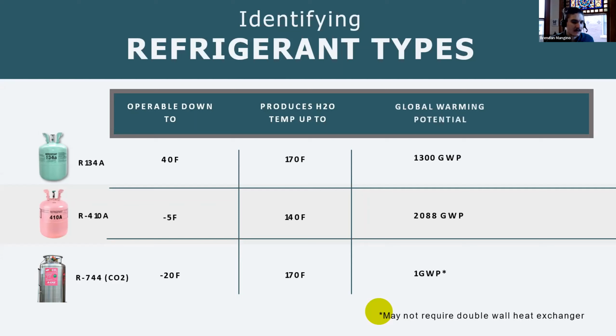And lastly, you got R744, which is CO2. So this can produce hot water at 170 or higher, and it can operate at really low ambient temperatures. Realistically, any ambient temperature in our climate, these will operate in. We have a couple of systems, and one of the ones we're going to talk about operated throughout the entire winter in upstate New York. They can go down to minus 20 degrees Fahrenheit, and we even have some quoted temperatures below that.